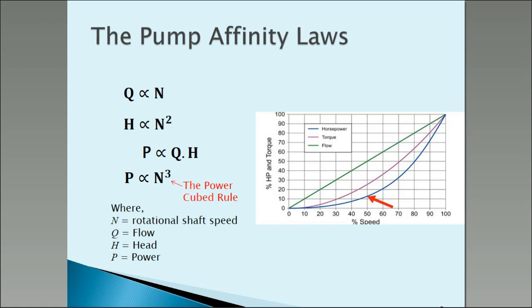Looking at the graph, the flow is proportional to speed — a straight line. The power is proportional to speed cubed, which is really good news. You can see with that red arrow: if you could halve the speed, you're going to have an eighth of the power you did to begin with. Some really big theoretical energy savings.